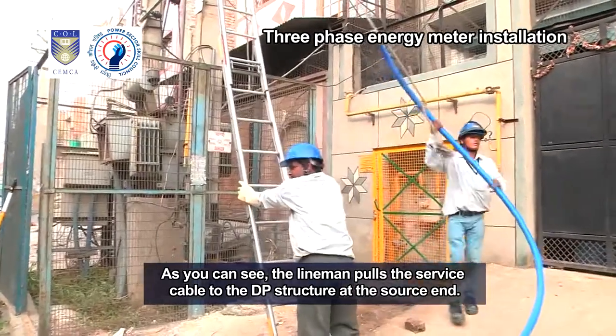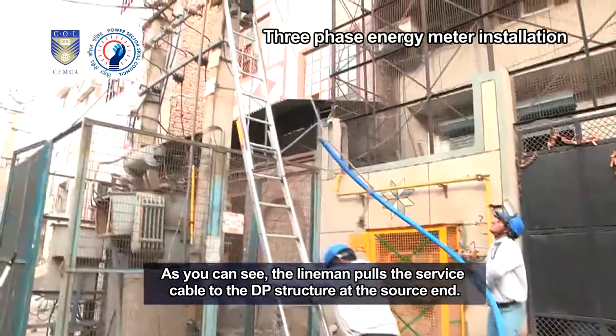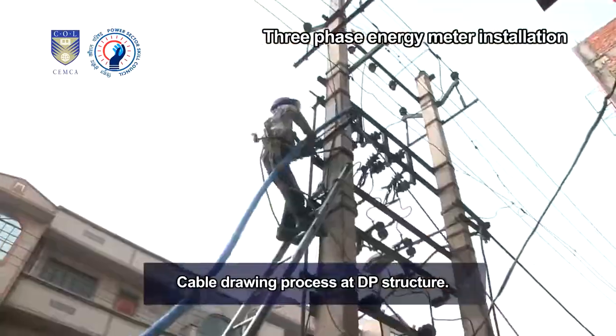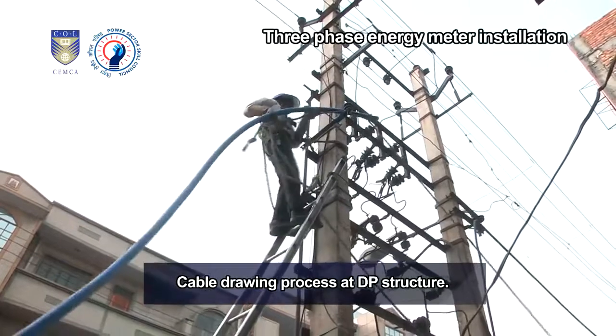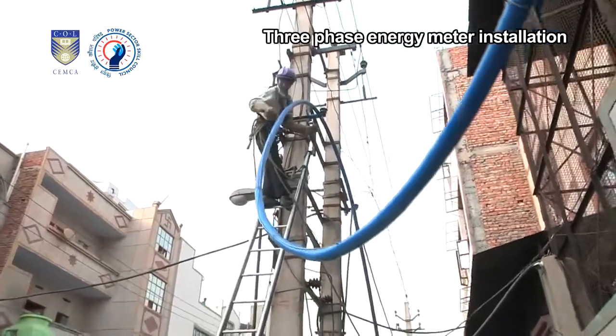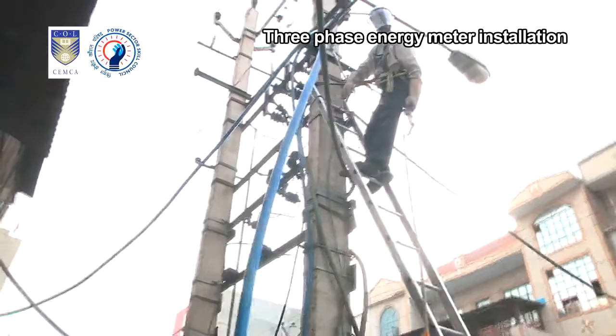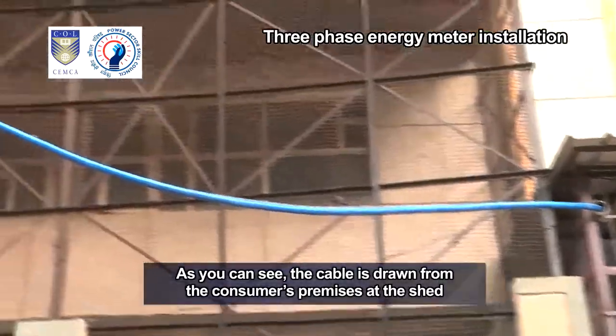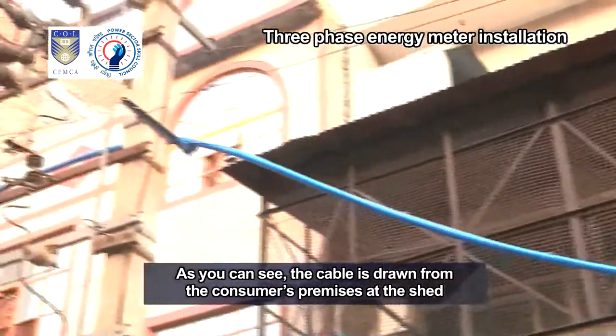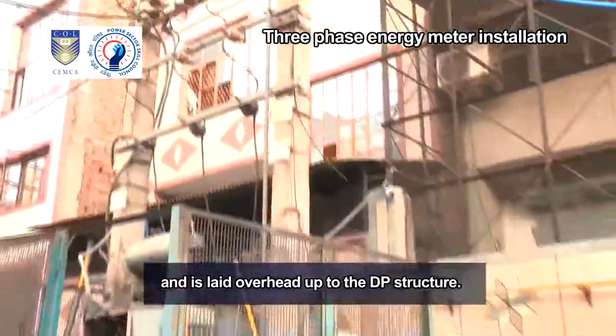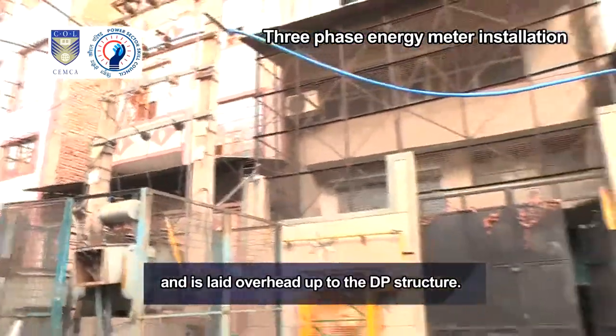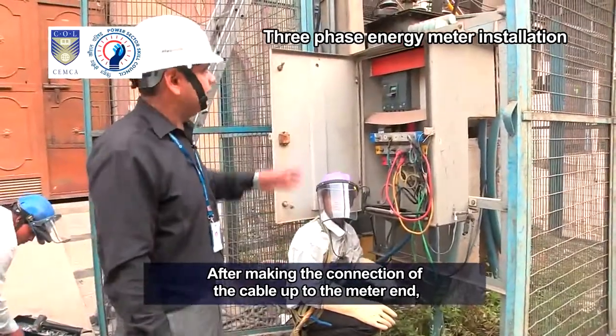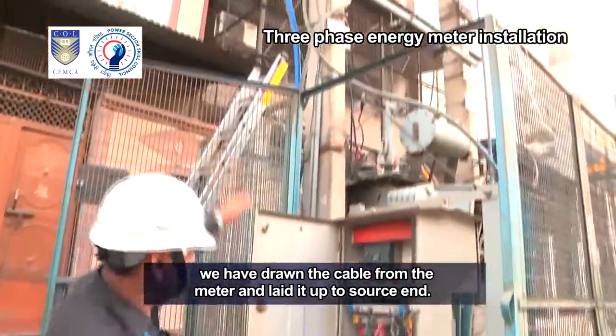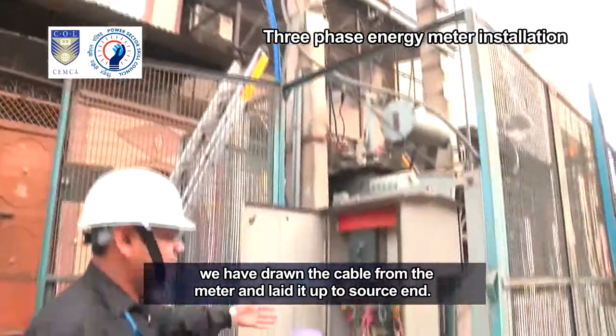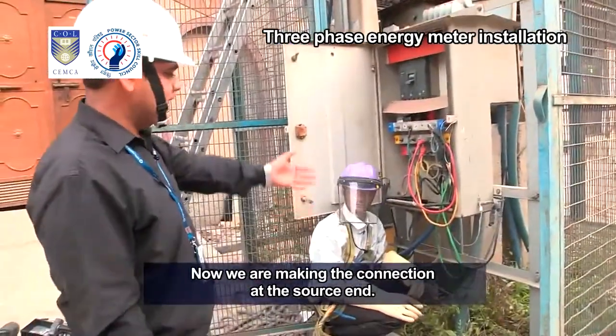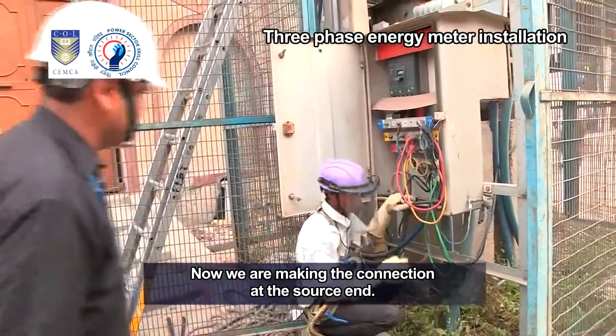As you can see, the lineman pulls the service cable to the DP structure at the source end. Cable drawing process at DP structure. As you can see, the cable is drawn from the consumer's premises at the shed and is laid overhead up to the DP structure. After making the connection of the cable up to the meter end, we have drawn the cable from the meter and laid it up to the source end. Now, we are making the connection at the source end.